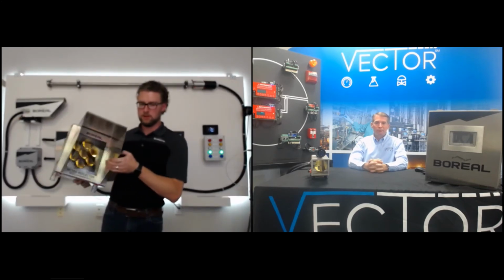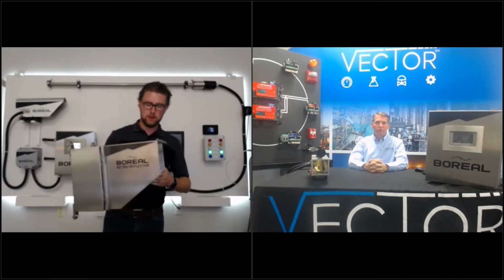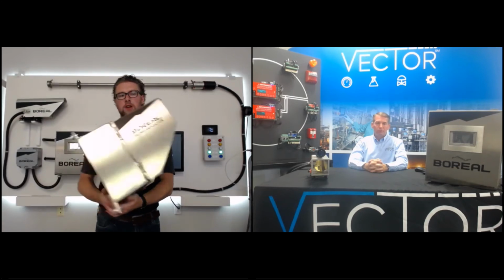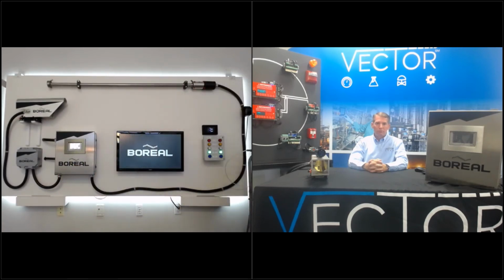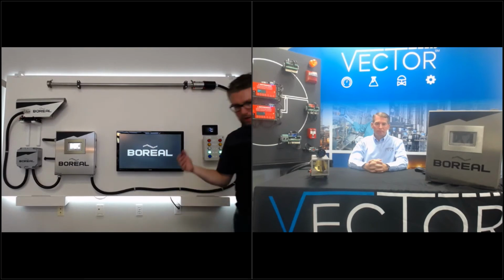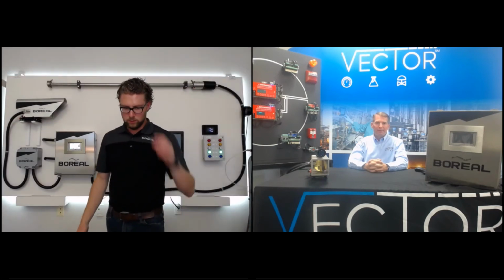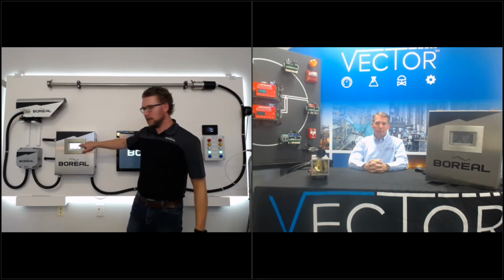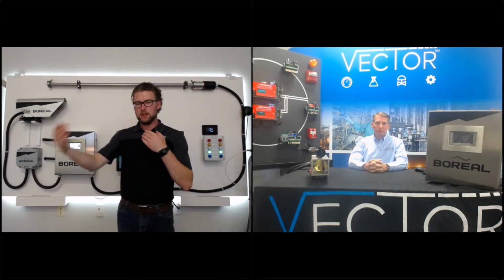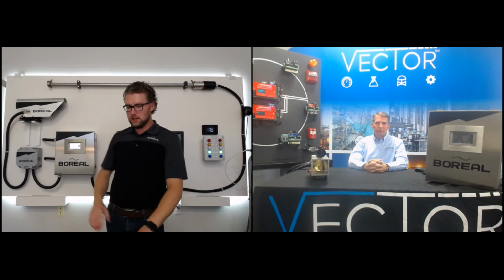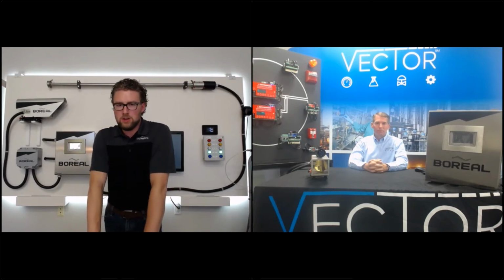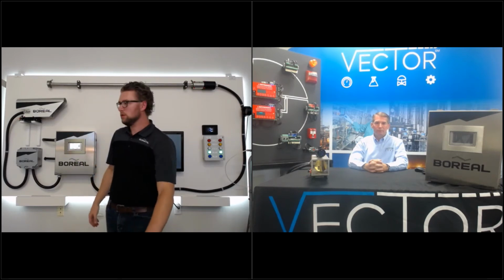Absolutely. And there's very aggressive rain and dust hood cowling on the retroreflectors as well, so it is more difficult for dirt, dust, debris, oil, whatever else to build up on these. But the system does have a light level bar, the amount of laser light it is receiving back. It is displayed on this HMI touchscreen. On your HART communication loop, the secondary digitized variable also displays the laser light level. So there's a maintenance call watch that you can have for this particular equipment.